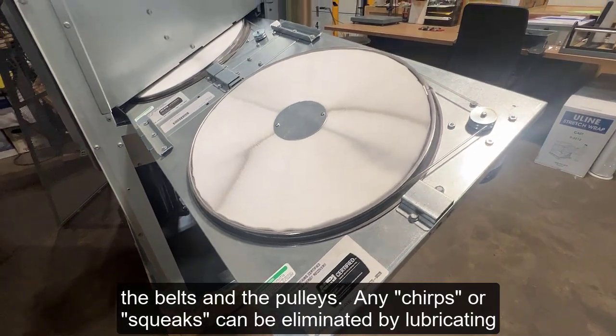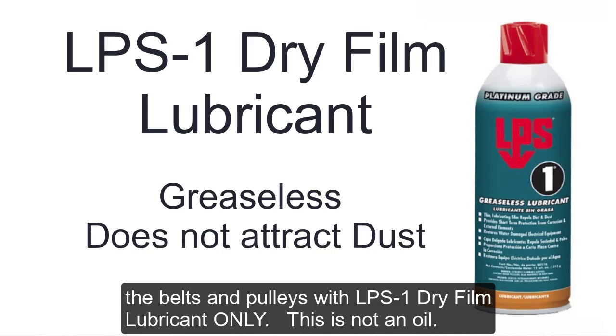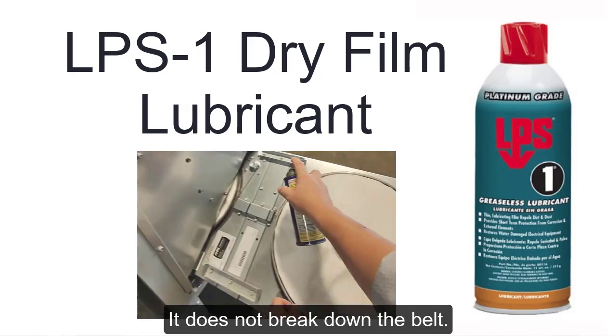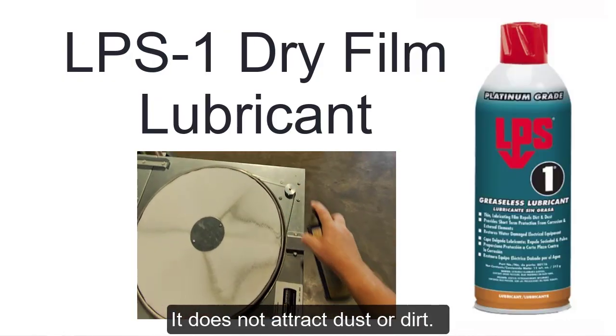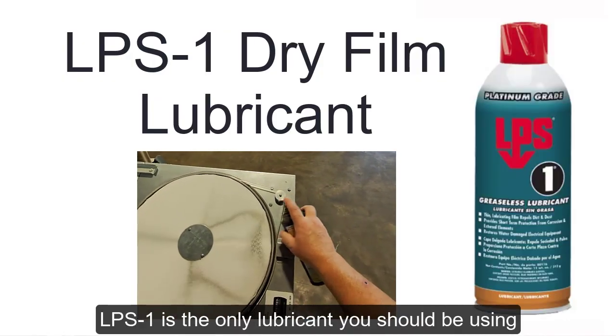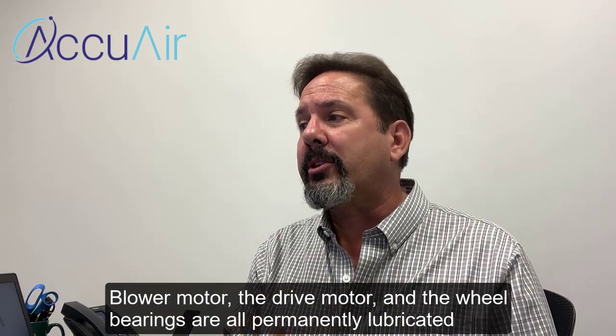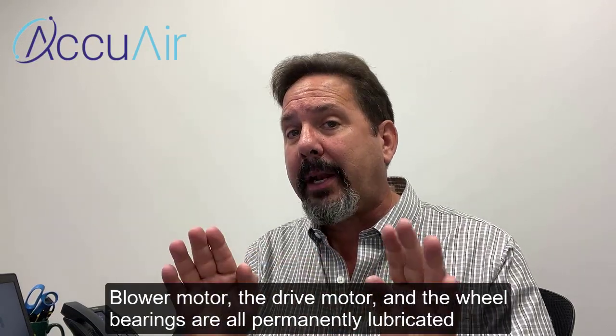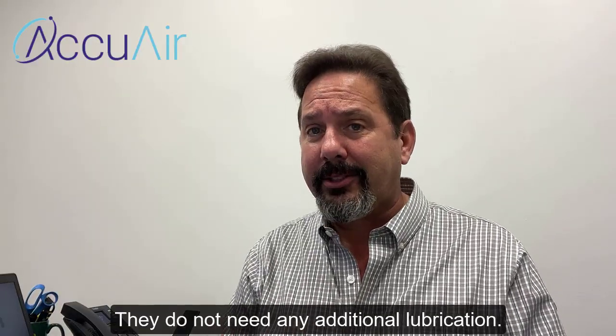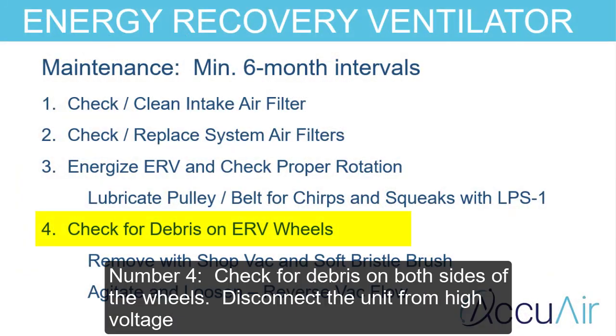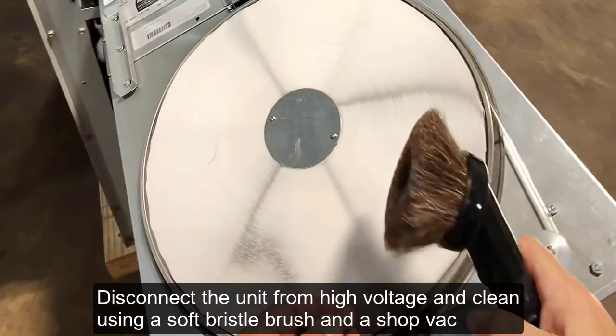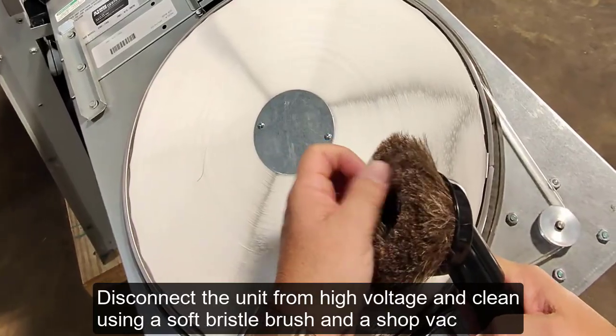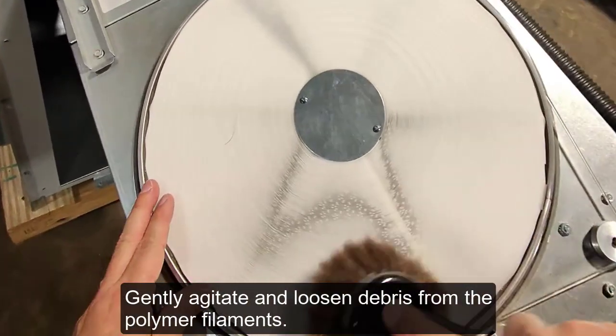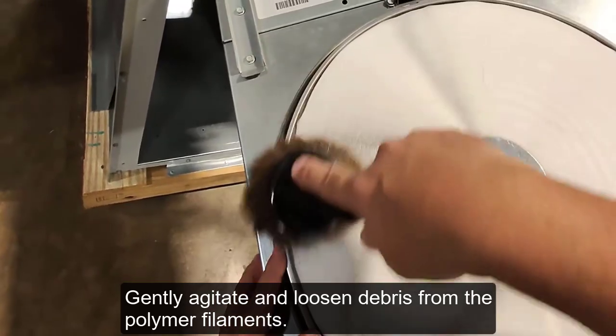Any chirps or squeaks can be eliminated by lubricating the belt and pulleys with LPS1 dry film lubricant only. This is not an oil, it does not break down the belt, it does not attract dust or dirt. LPS1 is the only lubricant you should be using. Blower motor, the drive motor, and the wheel bearings are all permanently lubricated. They do not need any additional lubrication. Number 4, check for debris on both sides of the wheels. Disconnect the unit from high voltage and clean using a soft bristle brush and a shop vac. Gently agitate and loosen debris from the polymer filaments.